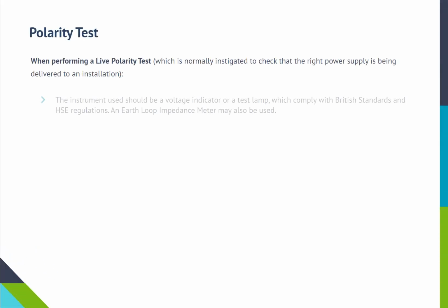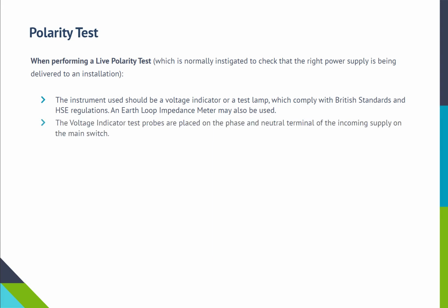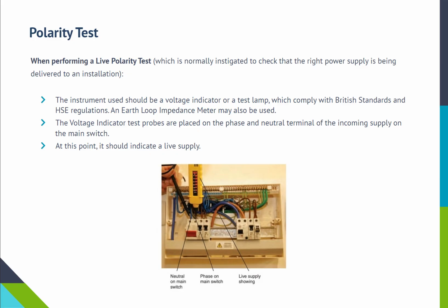When performing a live polarity test, which is normally instigated to check that the right power supply is being delivered to an installation, the instrument used should be a voltage indicator or a test lamp, which comply with British standards and HSE regulations. An earth loop impedance meter may also be used. The voltage indicator test probes are placed on the phase and neutral terminal of the incoming supply on the main switch. At this point, it should indicate a live supply.